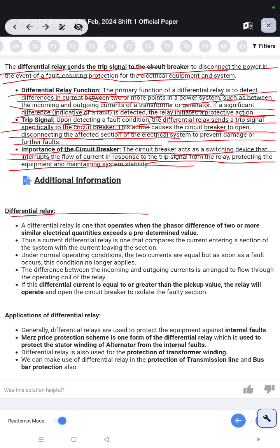A differential relay is one that operates when the phasor difference of two or more similar electrical quantities exceeds a predetermined value. Thus, a current differential relay is one that compares the current entering a section of the system with the current leaving the section.